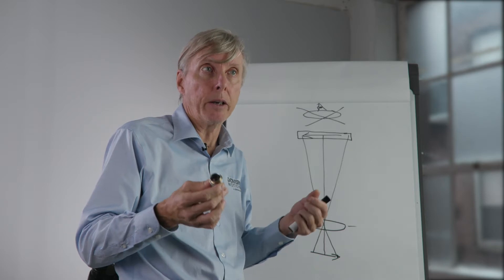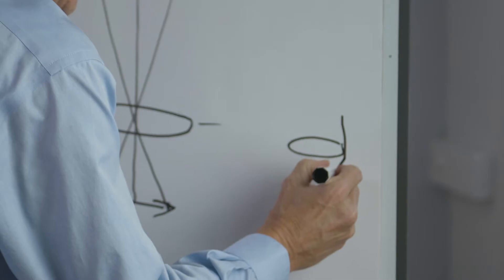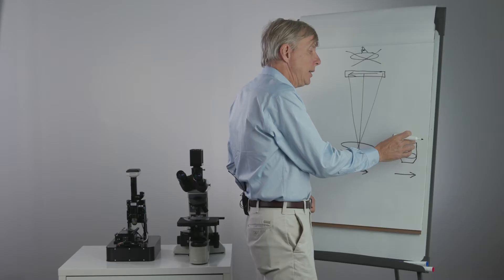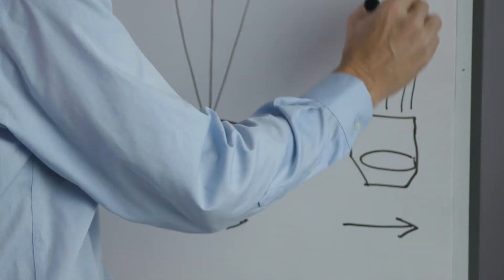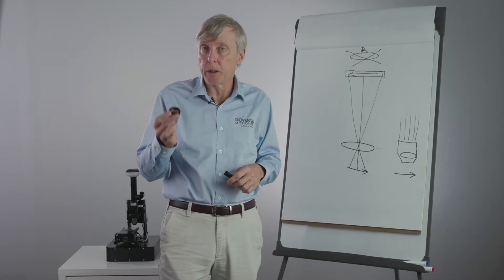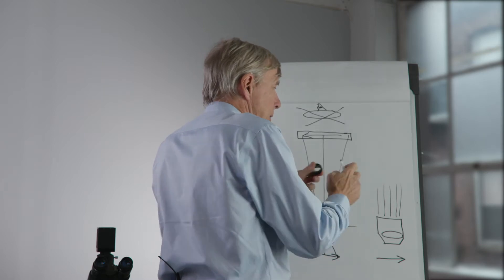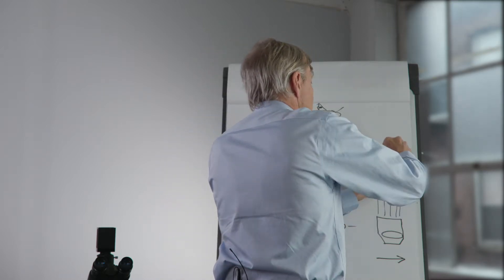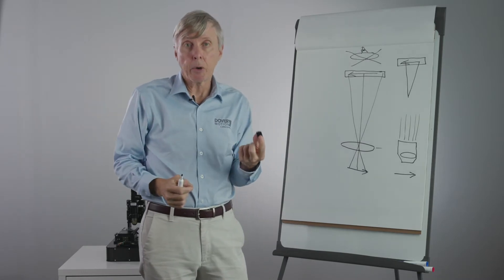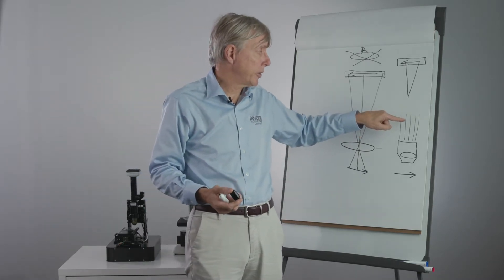In addition to the finite conjugate objective, there is the infinity corrected objective. In this case, the objective by itself does not form an image — the light coming out from any given point on the sample is parallel. This requires one additional optical element called a tube lens, which takes the parallel light from the objective and produces the image for the sensor. The advantage of an infinity corrected system is that you can place additional optical elements in this area, and with parallel light they don't produce the aberrations that would otherwise occur with angled light.